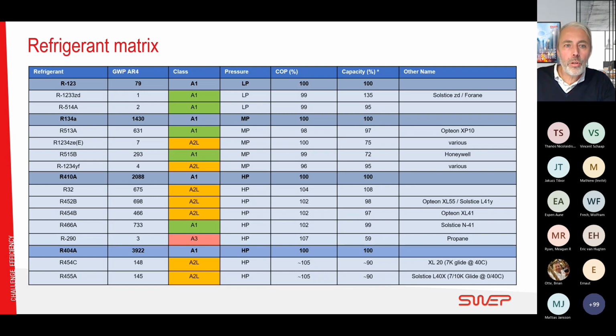Here is a refrigerant matrix for reference use. I have placed the most common or the legacy refrigerants in the first column, R-123 for low pressure. We have 134A for medium pressure, 410A high pressure, and then 404A high pressure as well. We have the GWP value here with AR4. We have the class, if it's flammable or not flammable, pressure, and then COP and capacity.